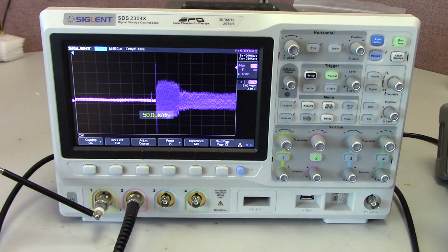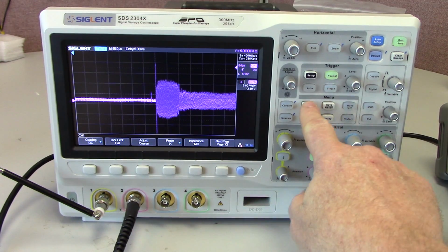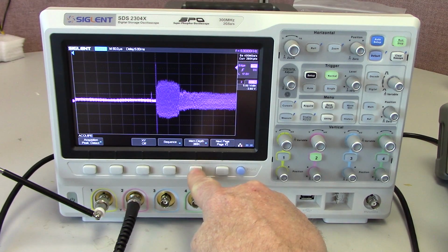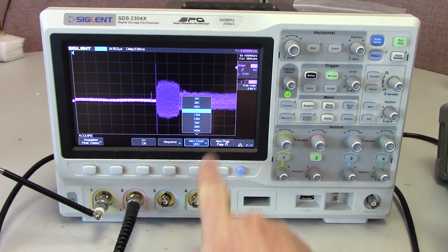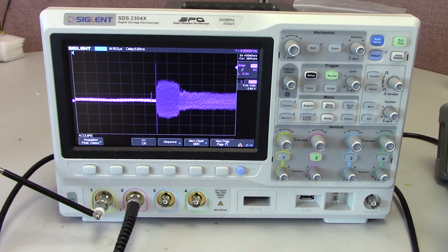So that is an example of just a small idea of what the sequence mode and the history function can give you. Again, I could get up to 80,000 frames that same way. I've got it set on low memory right now, so the dots are not real close together. As you'll see, I've got 280K set in the memory, but it goes to 140 meg, so I could do that also. I didn't want to wait for it to upload and download that data.